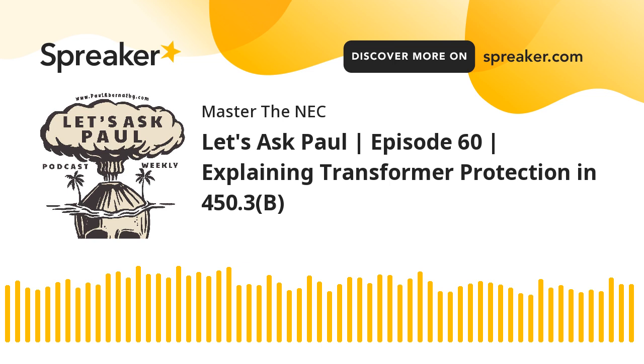So if we have that 45 kVA, and we're going to do it as continuous loads to keep it simple, we have 480 volt primary, 208 volt secondary. We need to determine what the secondary current rating is. Just like we did before, it's 45,000 VA. Divide that by, and what was the value we're going to use? 360.25. Why? Because that's the square root of 3 times 208 volts, because it is three-phase. And that ends up being 125 amps.